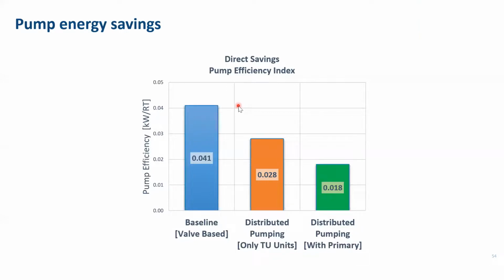So lastly, if we look at our kW per ton numbers, for a baseline valve system, or what the original condition was prior to the upgrade, this particular project went in phases. They took out the valves and replaced them with distributed pumps first. We've got some operating time and some operating data there. And then lastly, they reduced the size of the primary pump set. So we got to see that piece come together.